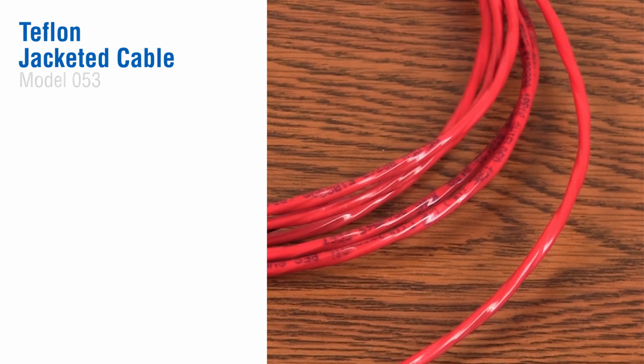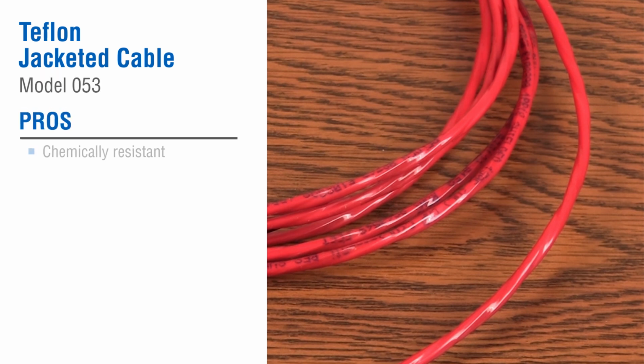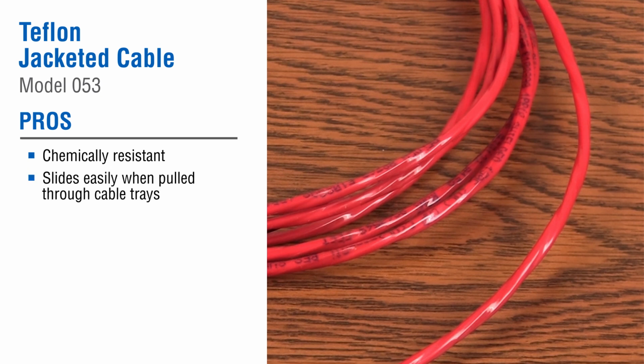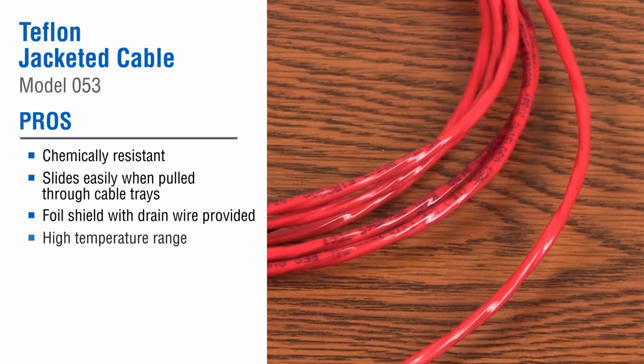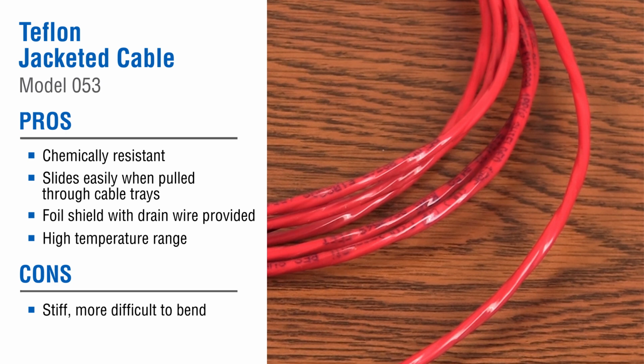Teflon jacketed cables, such as our cable type 053, have excellent compatibility in the overall spectrum of potential chemicals. They also slide easily through cable trays and have a foil shield with drain wire for proper grounding. Teflon can survive to 392 degrees Fahrenheit, 200 degrees Celsius. Therefore, in high-temp applications, we recommend it with a high-temp connector like the aforementioned AE or BP models. One drawback is this cable is stiffer with a larger bending radius. It's a little bit more difficult to manipulate around tight turns.